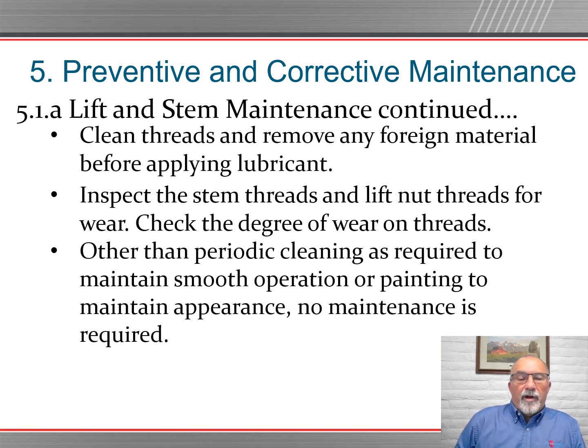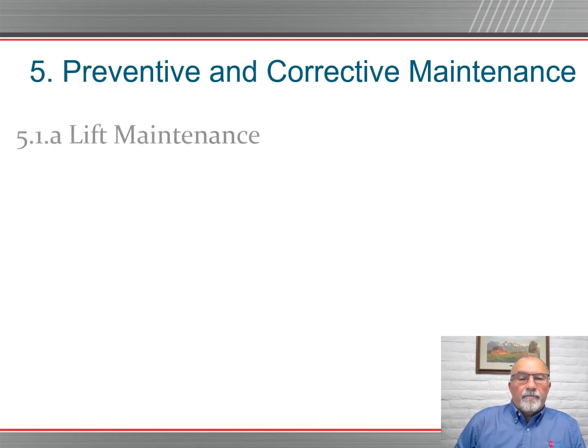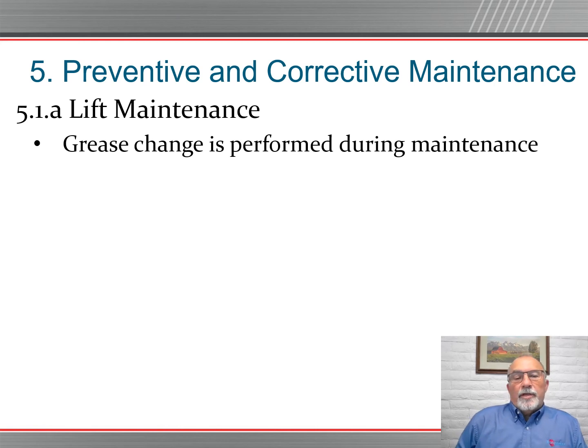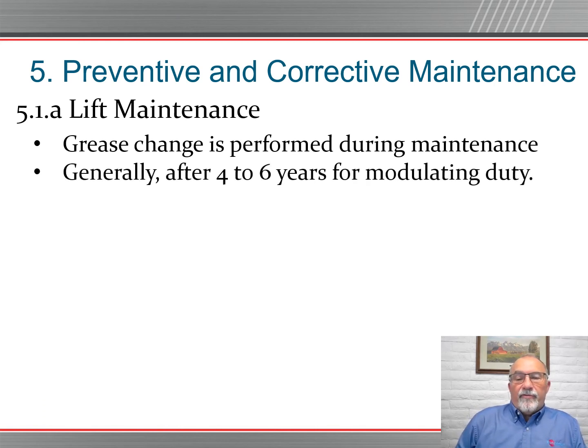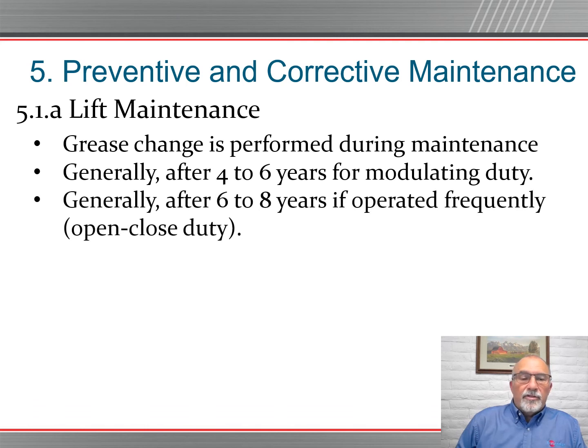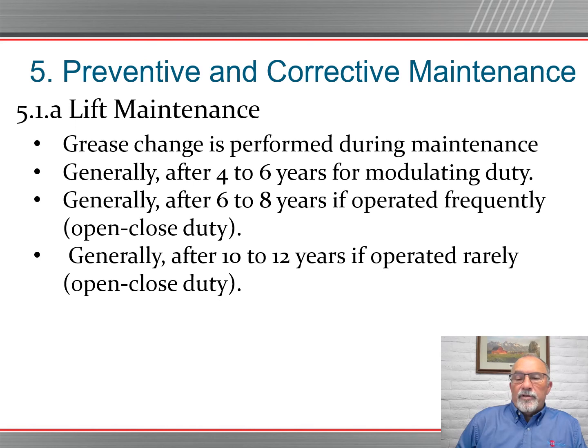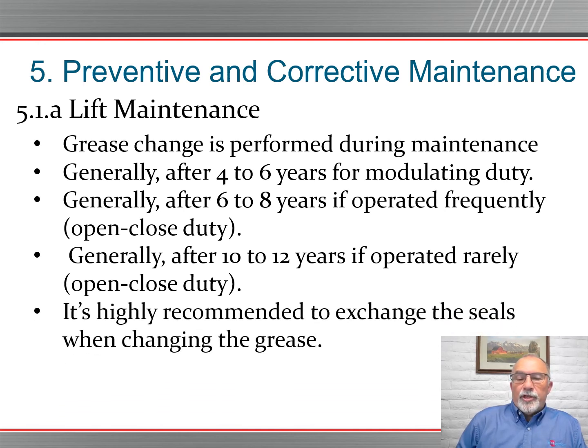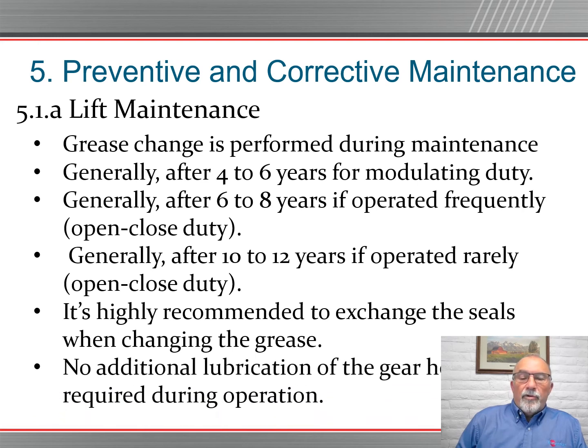Other than periodic cleaning as required to maintain smooth operation, or painting to maintain appearance, no maintenance is required on your butterfly valves. Change of grease is performed during maintenance, generally after 4 to 6 years of modulating duty or constant use, after 6 to 8 years if operated frequently on open and closed duty, and after 10 to 12 years if operated rarely on open and closed duty, such as 10 to 12 times a year. It is highly recommended to exchange the seals when changing the grease. No additional lubrication of the gear housing is required during this operation.